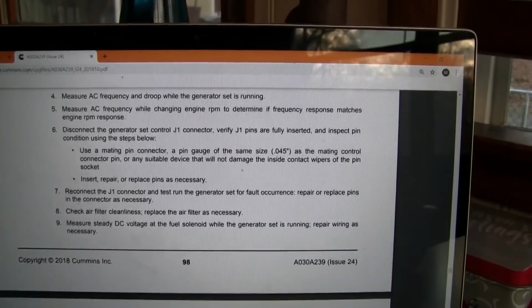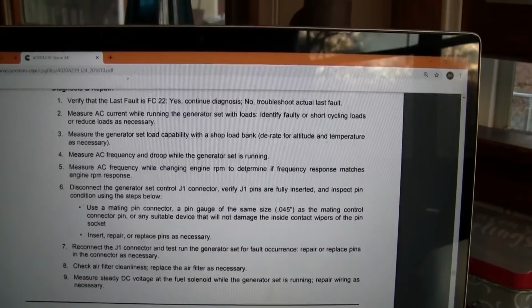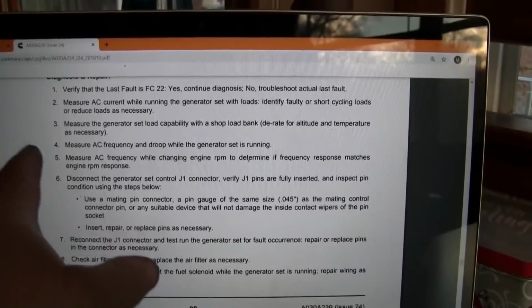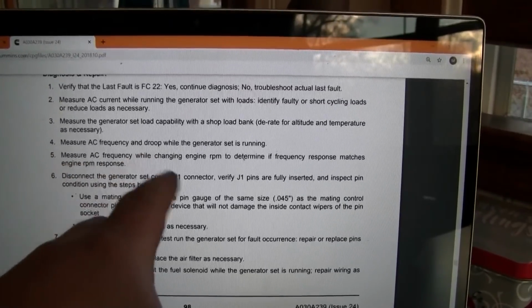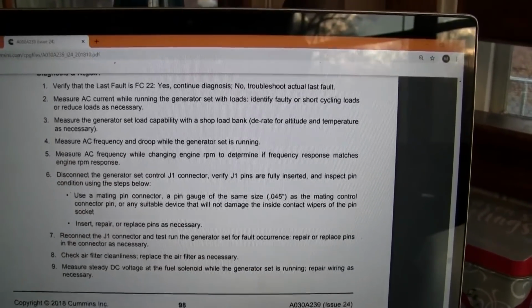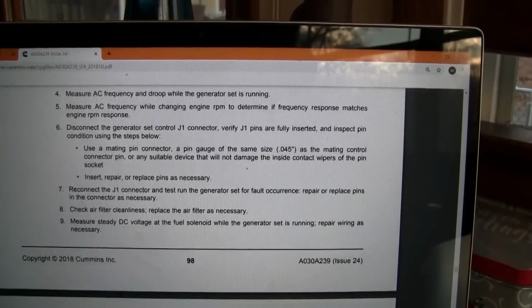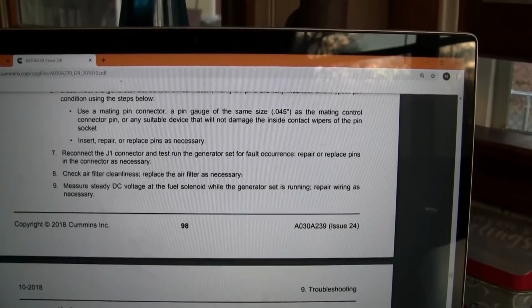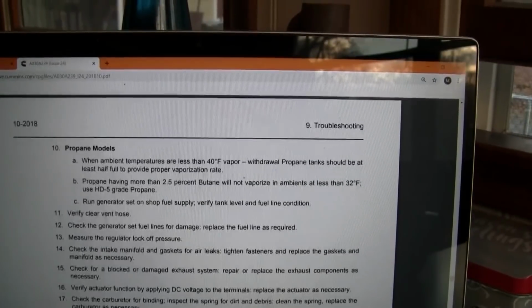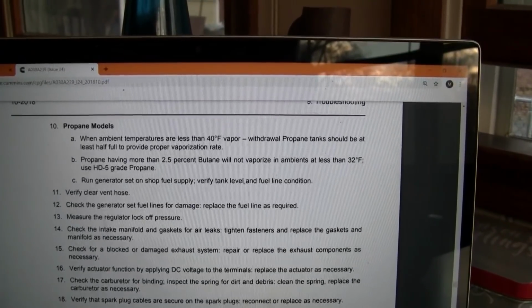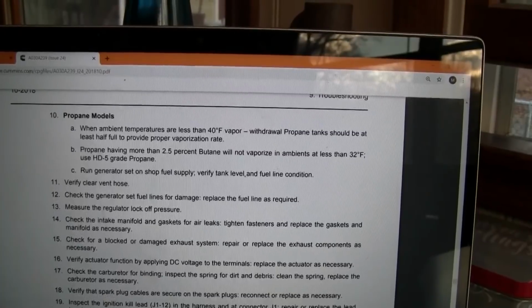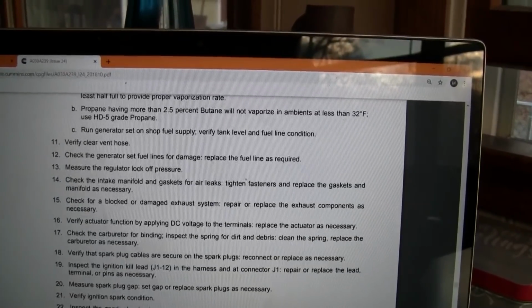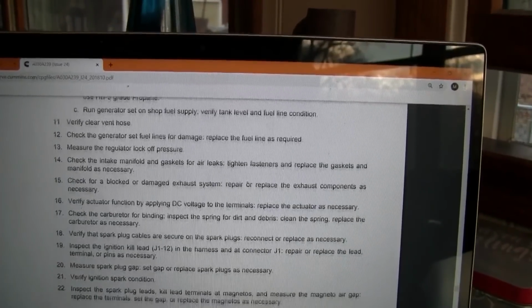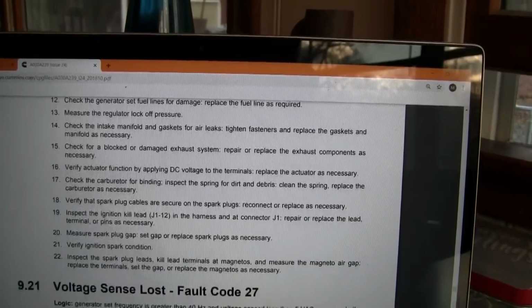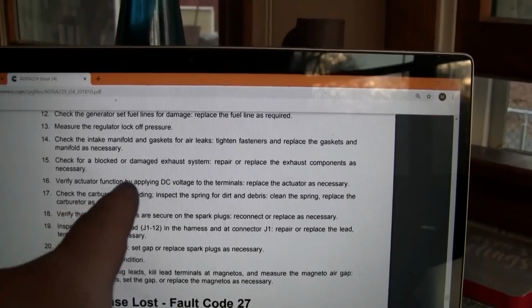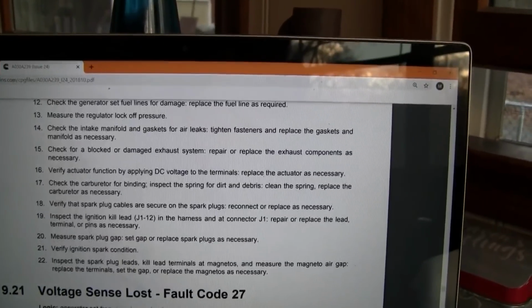So we were actually watching the controller when it shut down. So we know it was running about 59 hertz, which is acceptable. So there's a couple steps there: checking AC frequency, checking wire connections, some information there if you have a propane unit. Then of course fuel supply information, and then basic checks for the governor actuator.